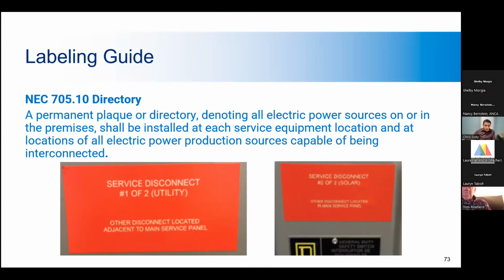Another thing that you have to label is the service disconnects. They have to be labeled with permanent plaques. You can see here, this is a great example because it has service disconnect 1 of 2. So whoever's working on it knows exactly how many there are, and it identifies which one it is. So you have the utility disconnect and the solar disconnect. And this ensures that anyone working on the system knows how to shut down the system later on when they're working on it.